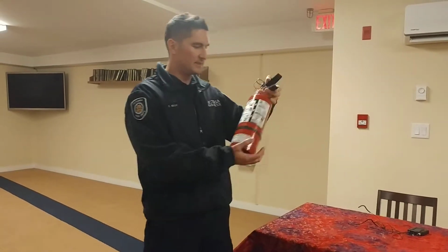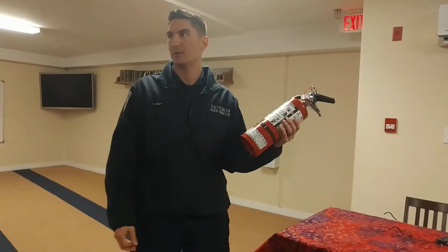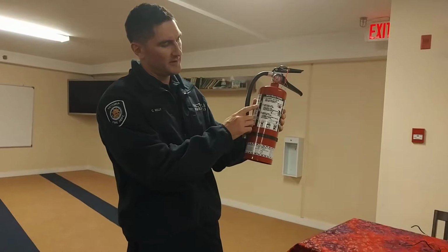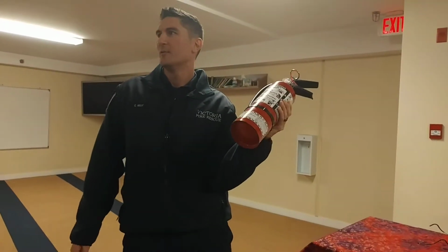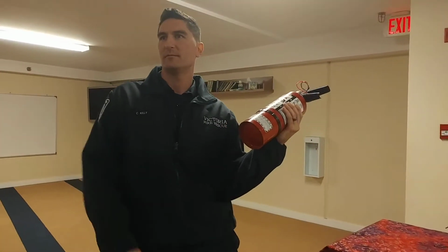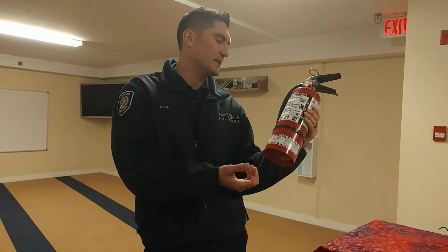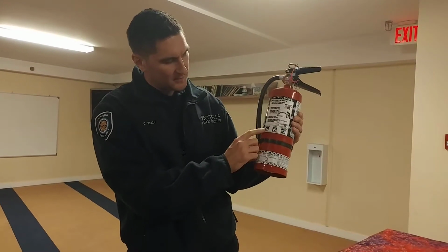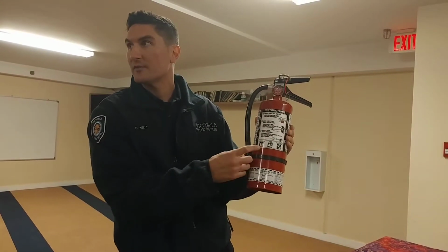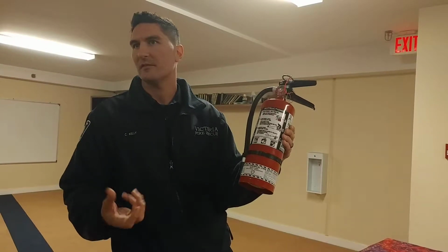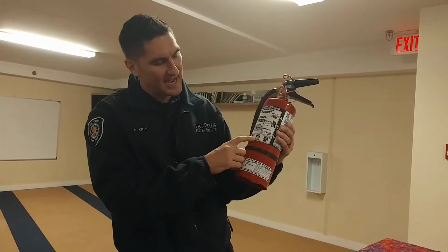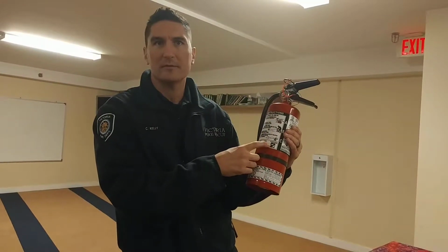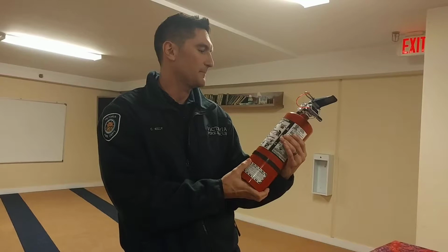Awesome. The way to distinguish whether you have the proper extinguisher for the proper type of fire is, there's a few ways. They'll label it with the lettering A, B, C, but if you can't remember what the A stands for, what the B fuel classification is, or what the C classification is, it also has little pictograms. This one's a trash bin with campfire logs indicating ash and things of that variety. This has a gas tank, so a flammable liquid. And then we've got an electrical plug for any electrical or circuitry type of thing.